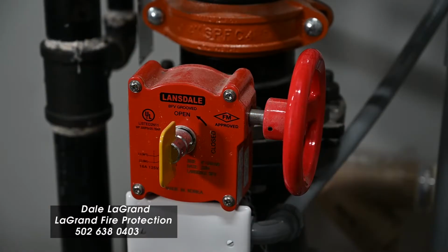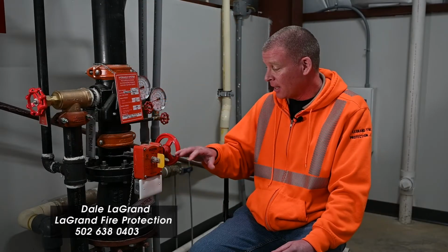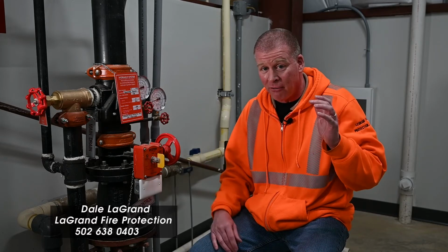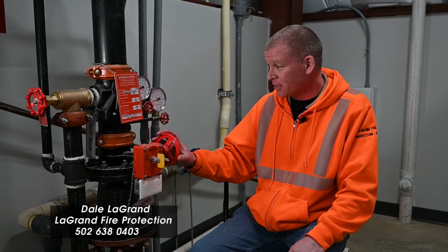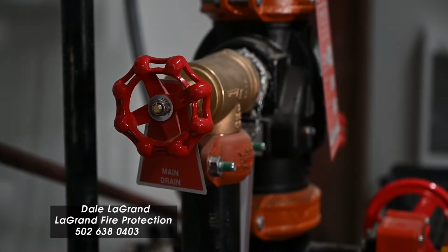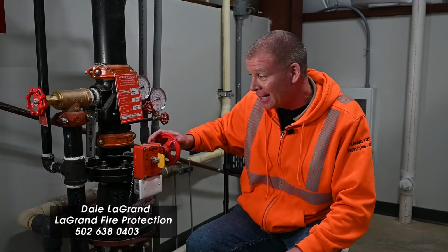If you turn this clockwise, this indicator here will show that it's closing, and that will shut off the water to the system. Only shut it off if you have an accidental discharge that you know happened in the office. Somebody accidentally hit something, or maybe back in your rubber room, somebody hit something on a rack or whatever. Then you come in here and shut this off. What you want to do is shut that, open this main drain, turn it to the left loose, right tight to shut it, left loose to open this. This will take the pressure off the system and keep you from having more water damage than you need.